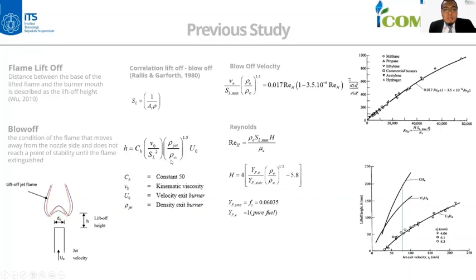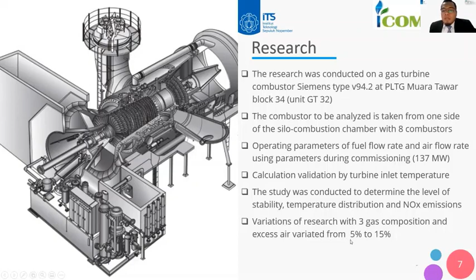The research was conducted on a gas turbine combustor Siemens type V94.2 at PLTG Muara Tawar, Block 3-4. Number 2, the combustor to be analyzed is taken from one side of the silo combustion chamber with 8 combustors. The operating parameters of fuel flow rate and air flow rate use parameters during commissioning, approximately 137 megawatt. Then calculation validation by turbine inlet temperature. Next, the study was conducted to determine the level of stability, temperature, and NOx emission. Last, the variation of research is 3 gas compositions and excess air varied from 5% to 15%.